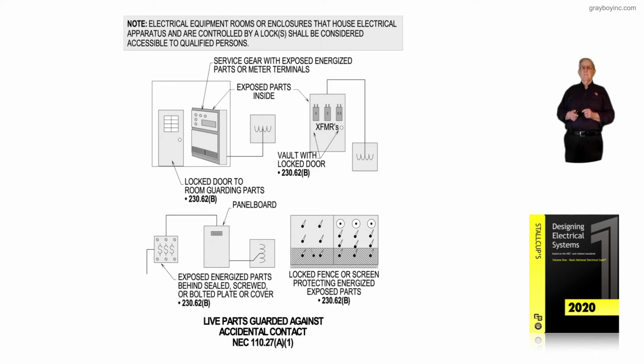And notice it has a locked door in accordance with 230.62(B). Both of them are really guarding these live parts as services. When you see 230, if it was 240, that'd be overcurrent protection. If it was 250, then naturally that deals with grounding and bonding. But the door again is guarding those exposed live parts on those transformers in that vault.